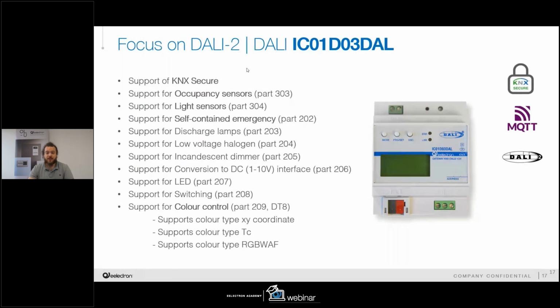Here in this slide we can see some detailed information regarding what the gateway can control, starting from KNX Data Secure. This device is already compatible with KNX Data Secure, meaning that you can encrypt your telegrams and have a secure project with KNX. In addition, we can see how we can integrate motion sensors, occupancy sensors, and lighting sensors, meaning that we can activate also different functions in our DALI system now, like the custom dimming function, of which we will see an example later.